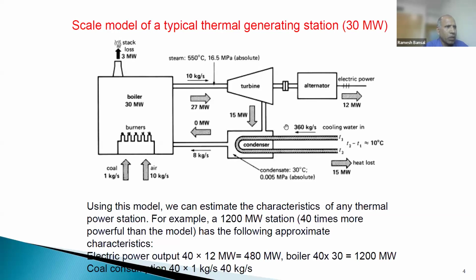Then another point - when we are talking about coal-based power plants, you can see that a significant quantity of water is required for cooling purpose in the condenser. So for 1 kg per second of coal, it requires 360 kg per second of cooling water. So obviously this plant will be located close to some river.